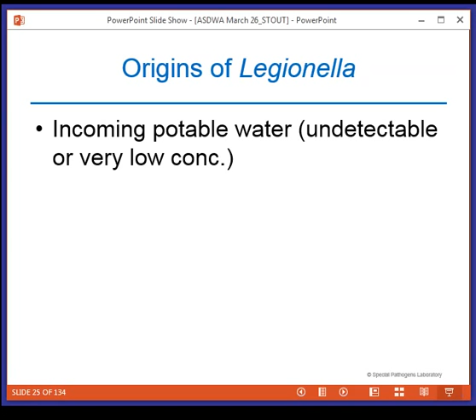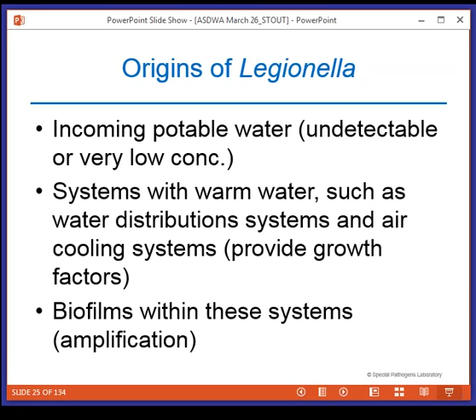How does Legionella get into our water in the first place? Some of this you may know, some you may not. Legionella is really coming into buildings in the source water, but at basically undetectable or very low concentrations. In my experience, when we sample the cold water coming into the building after the meter, we don't find much Legionella. But when that bacteria gets into the warm water distribution systems and cooling towers, that's where it grows to high numbers, or is amplified. Biofilm within these systems certainly contributes to that - it survives in both the biofilm phase and the bulk water, or planktonic, phase. It's the warm water and nutrients that allow it to multiply to high numbers.